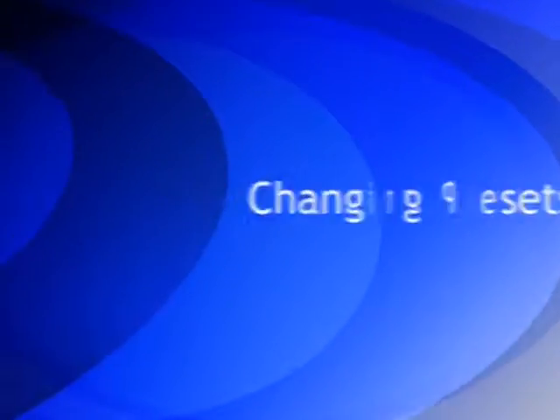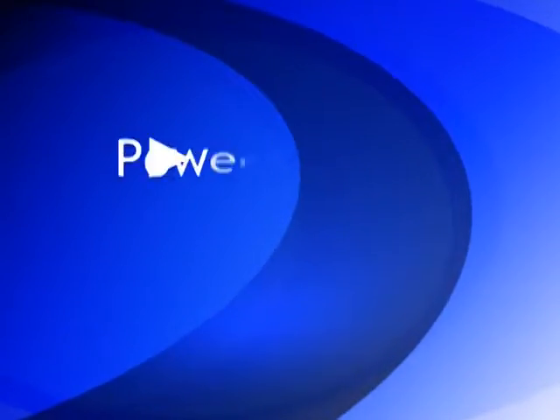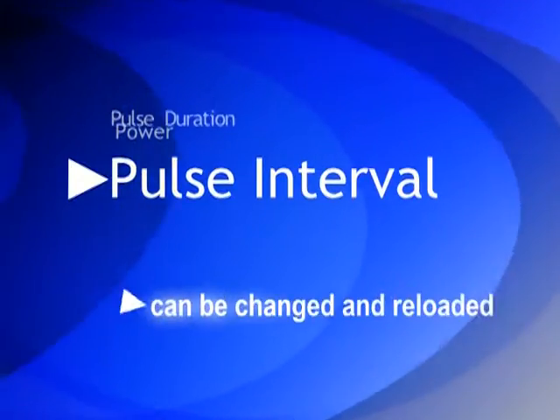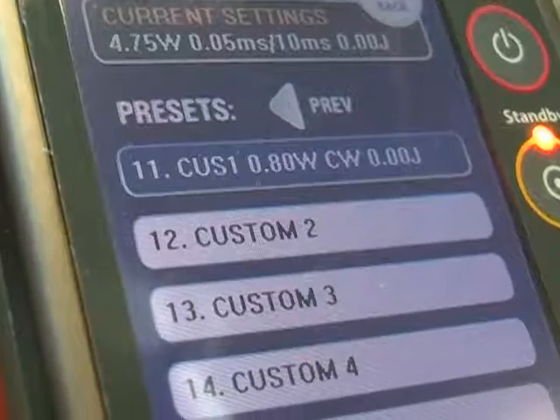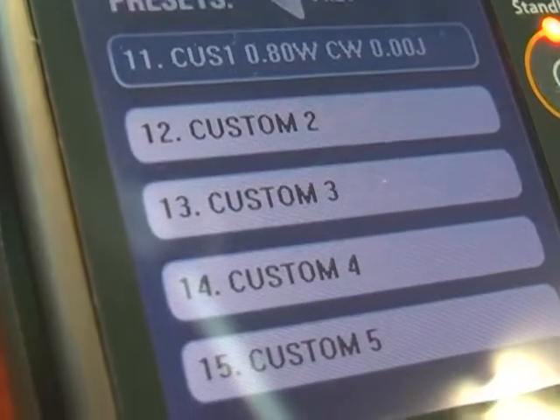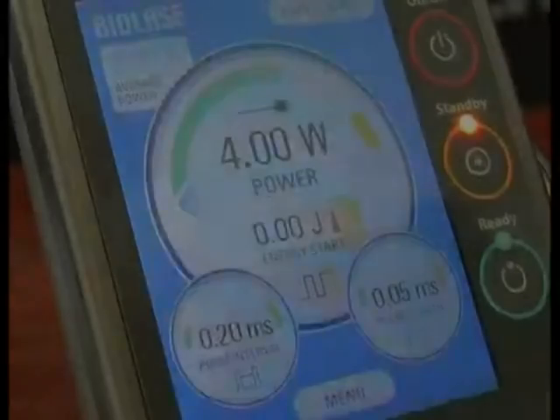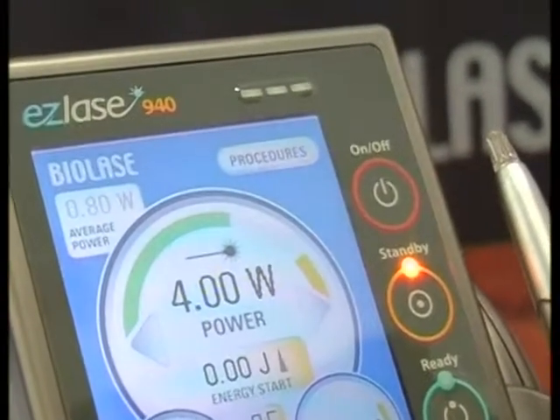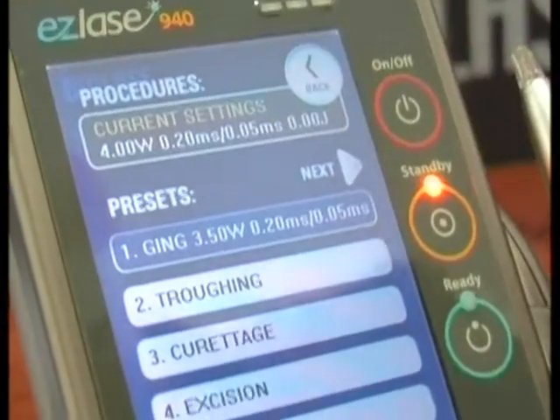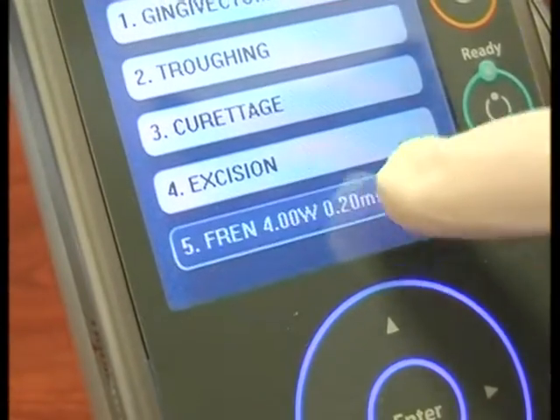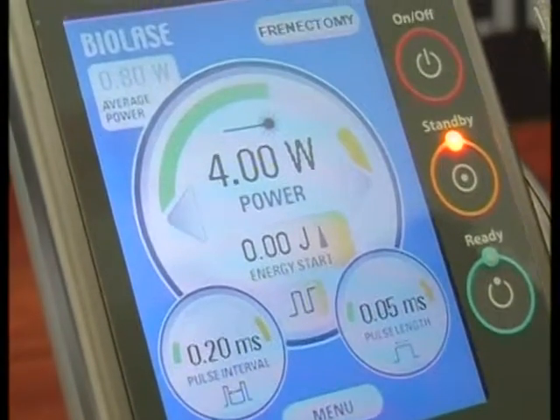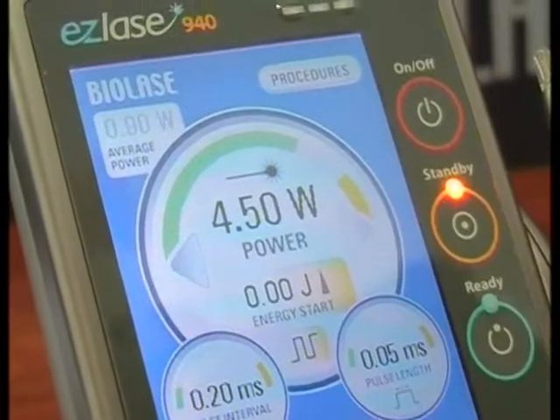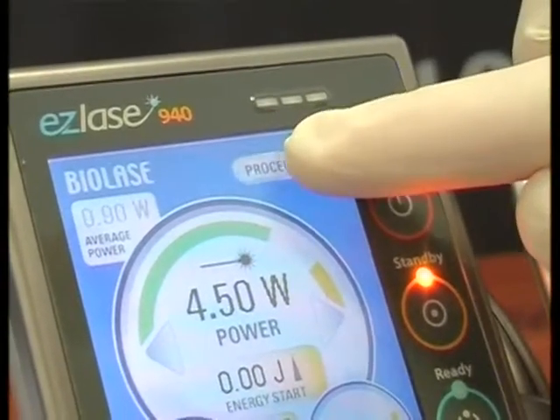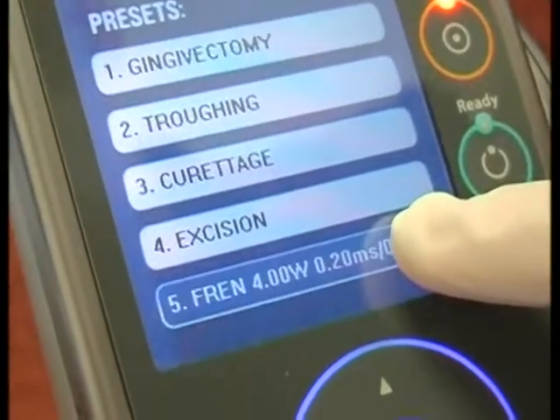Changing preset parameters and adding customized presets. You can change the factory presets for power, pulse duration, or pulse interval for any particular procedure, or load your own preset parameters into the custom presets numbered 11 through to 15. First, select and upload the procedure you want to change. And then make the changes of any of the parameters we have just explained. Now, go back to the procedures menu and hold the button of the procedure you wish to change for 3 seconds and it will update.